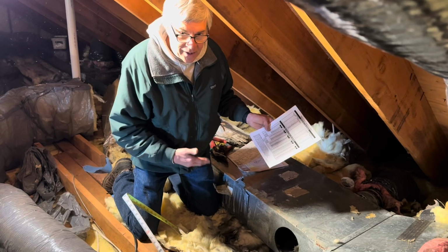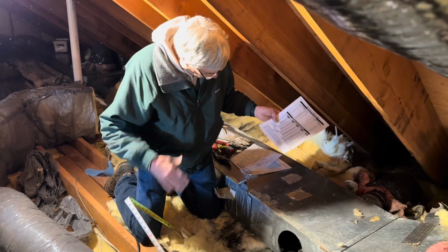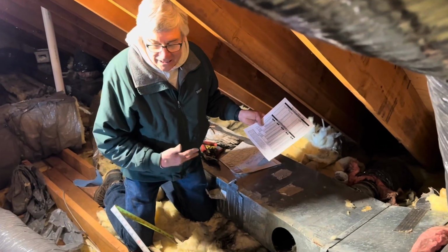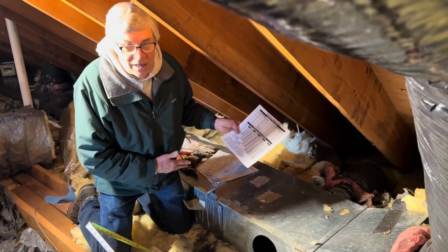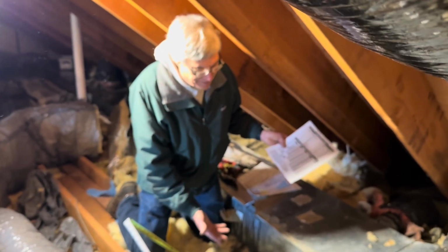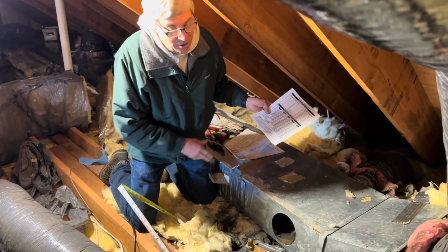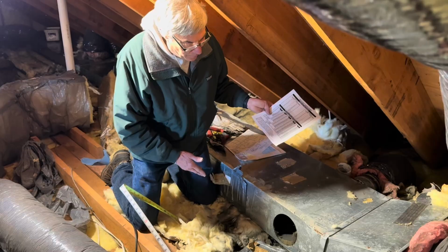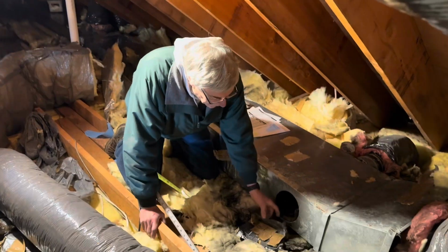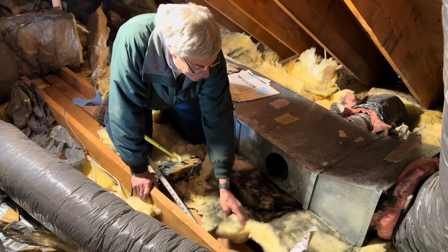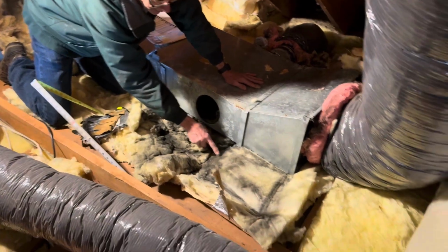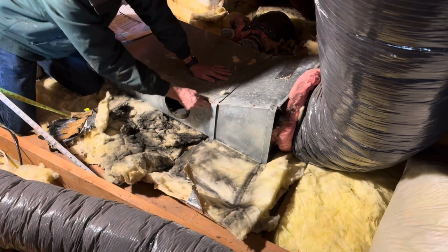So the correct way to do this, in my mind, based on the book that tells me how to do this stuff, called Manual D, is we want an unlined duct, we want an actual measured size, and then we want to seal the duct and then measure and then wrap it correctly. So this duct, when we arrived, was neither sealed nor wrapped correctly, which is indicated by all this black insulation here, all right? So what happened is, if you look at this line right here, it corresponds with this.